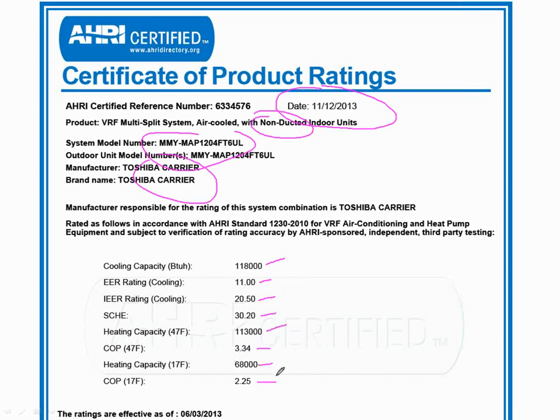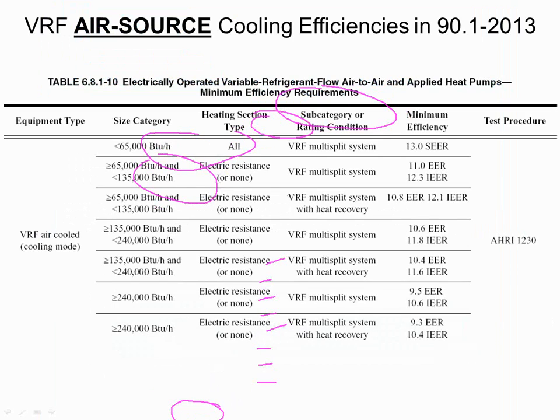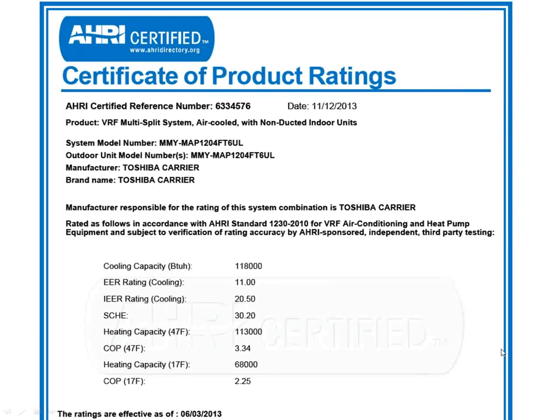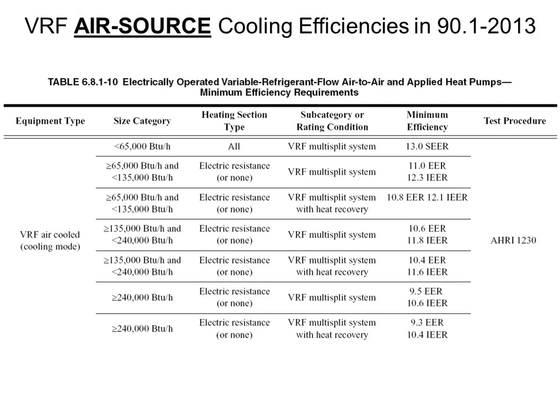So you can see this unit lost, I don't know what it is off the top of my head, 40% of its capacity as I dropped from 47 to 17 degrees. It will also tell you when this particular system was rated. So this is a November 2013 printing of a June 2013 actual rating data. That way, if you ever have to go back in time or if things change, you know what all your data was based on. I would highly recommend with any system you do on that AHRI directory that you print off the certificate, because things do change and you want to have that most current data, or the data you based it on, in your file.